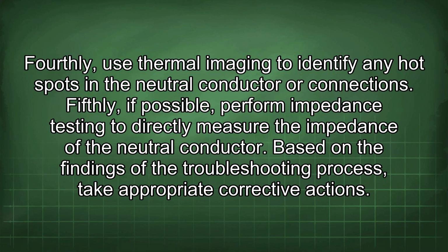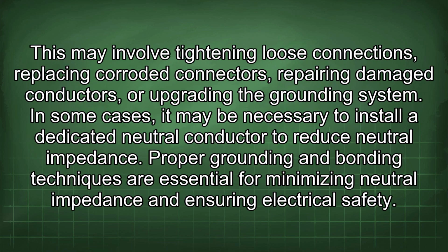Based on the findings of the troubleshooting process, take appropriate corrective actions. This may involve tightening loose connections, replacing corroded connectors, repairing damaged conductors, or upgrading the grounding system. In some cases, it may be necessary to install a dedicated neutral conductor to reduce neutral impedance. Proper grounding and bonding techniques are essential for minimizing neutral impedance and ensuring electrical safety.